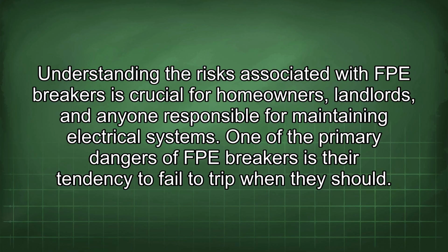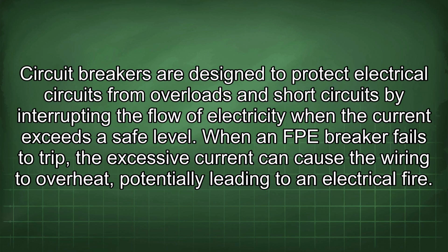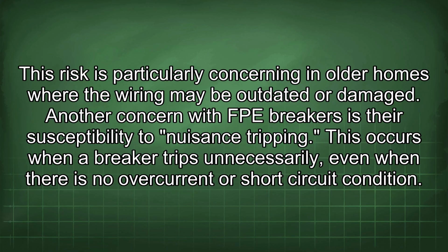One of the primary dangers of FPE breakers is their tendency to fail to trip when they should. Circuit breakers are designed to protect electrical circuits from overloads and short circuits by interrupting the flow of electricity when the current exceeds a safe level. When an FPE breaker fails to trip, the excessive current can cause the wiring to overheat, potentially leading to an electrical fire. This risk is particularly concerning in older homes where the wiring may be outdated or damaged.